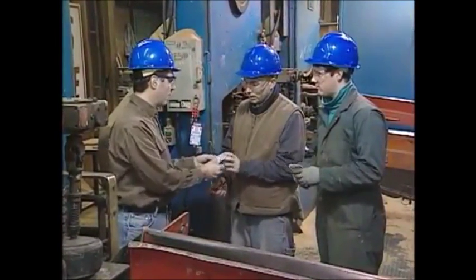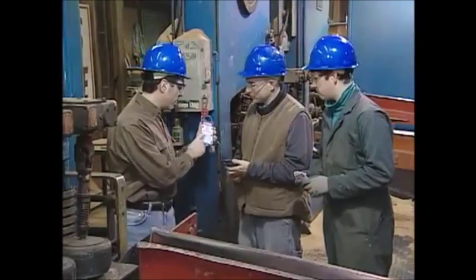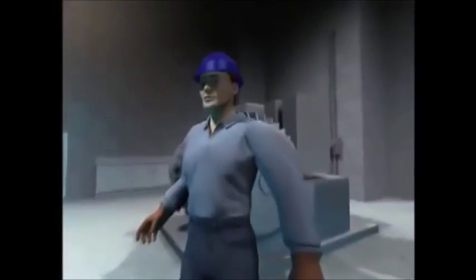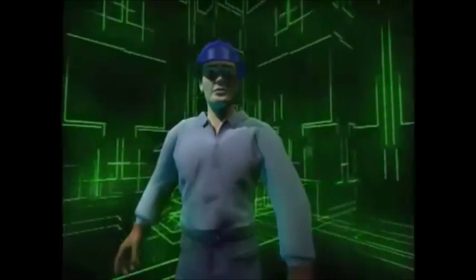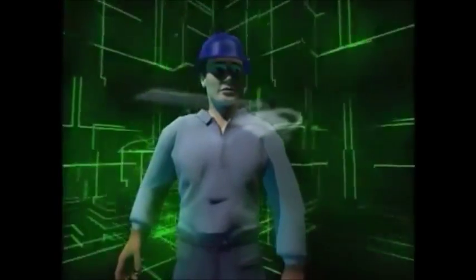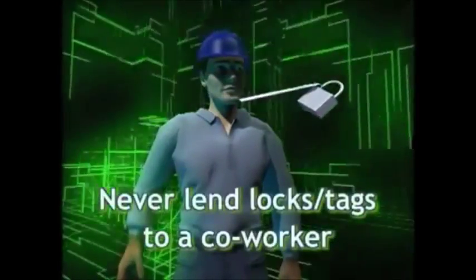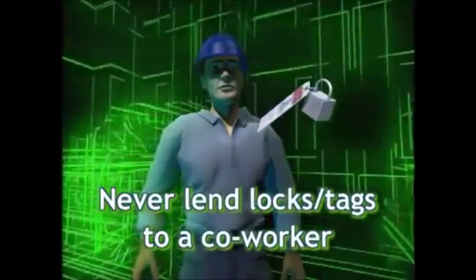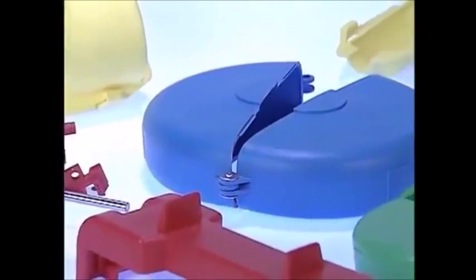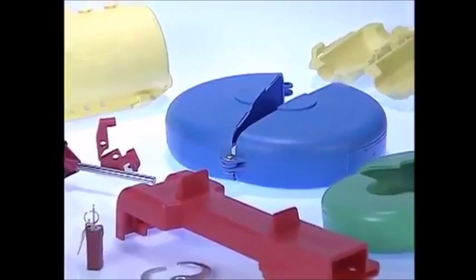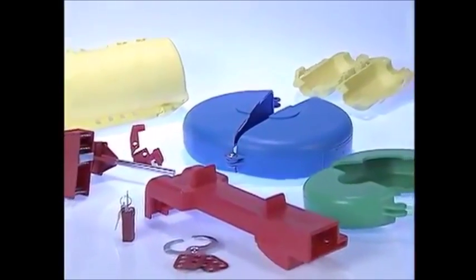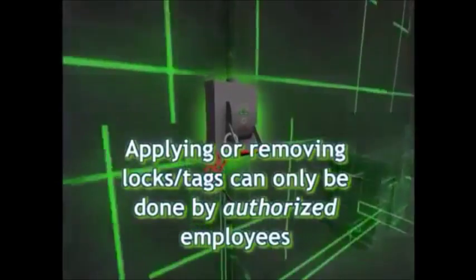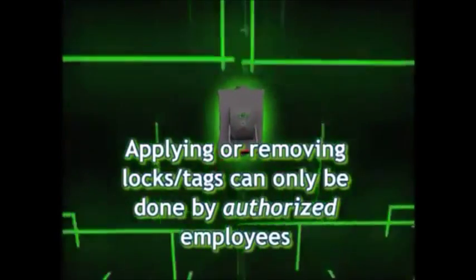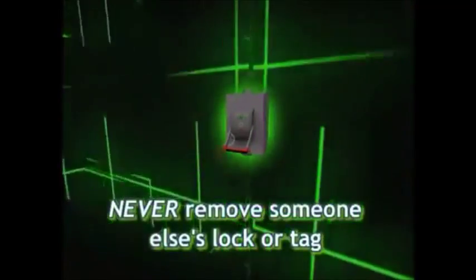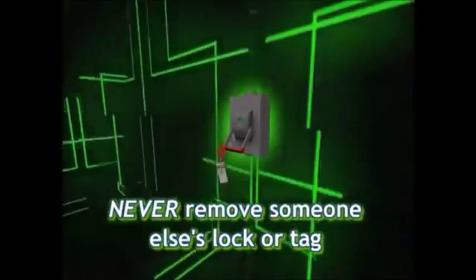These items must be long-lasting and not easily removed. Each lock and tag should have some way to identify who it belongs to. Each person may be issued a lock or series of locks. Never lend it to a coworker. Devices used for lockout tag-out should be used solely for that purpose and should never be used for anything else. Applying or removing locks and tags can only be done by authorized employees. Never remove someone else's lock or tag.